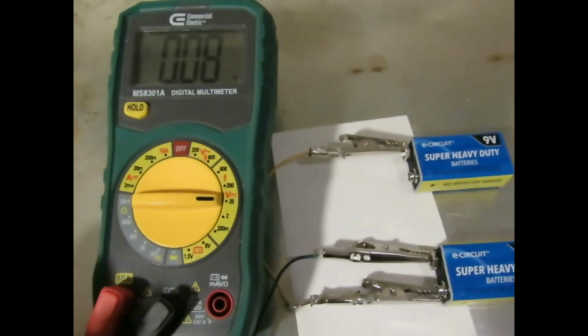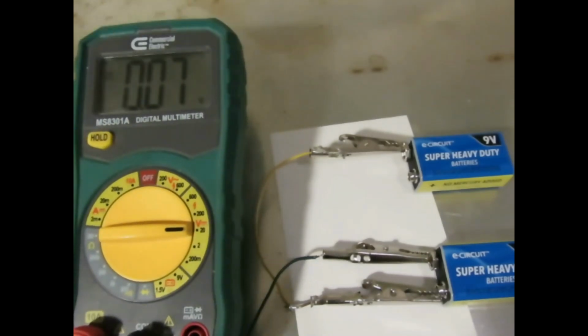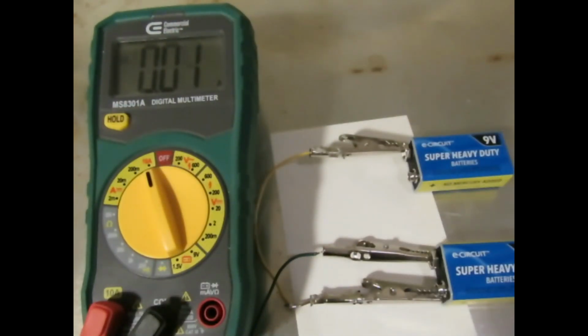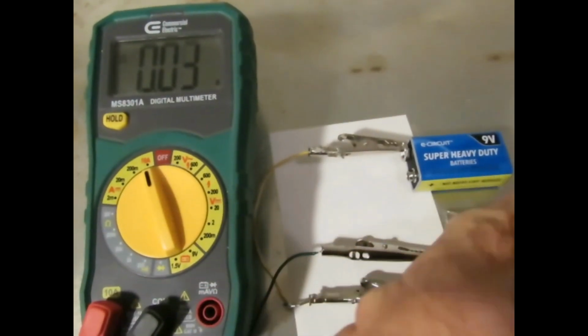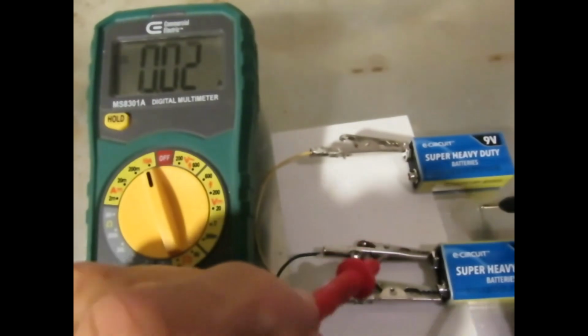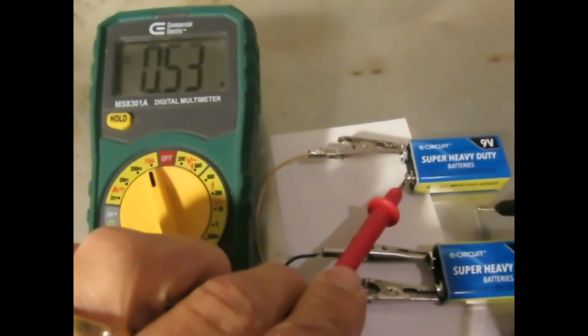Now we're going to pull this probe out and move it over to amperage, to the 10 amp port, and change the switch over to 10 amps. We're not going to get 10 amps, but the other measurements are in milliamps, so I'm going to start with the largest, and if it doesn't read, I'll move down. And we are at 0.53 amps.